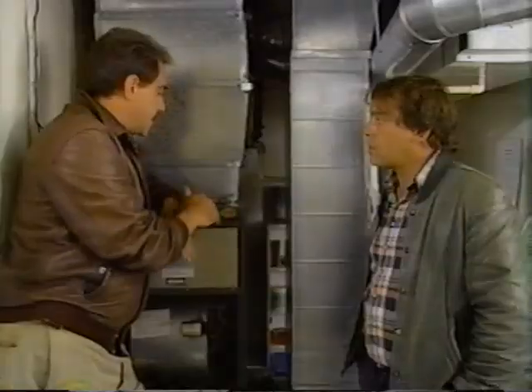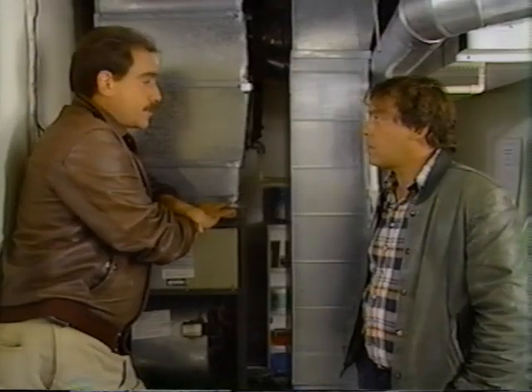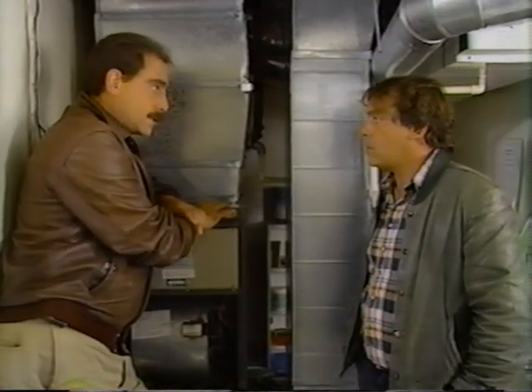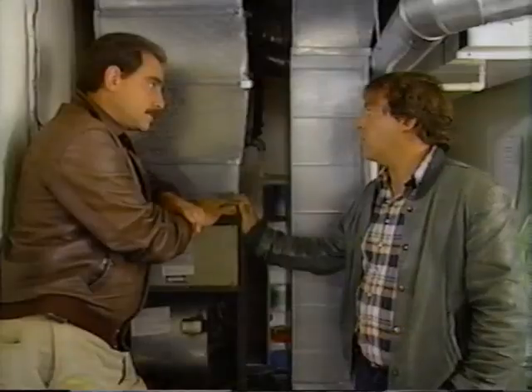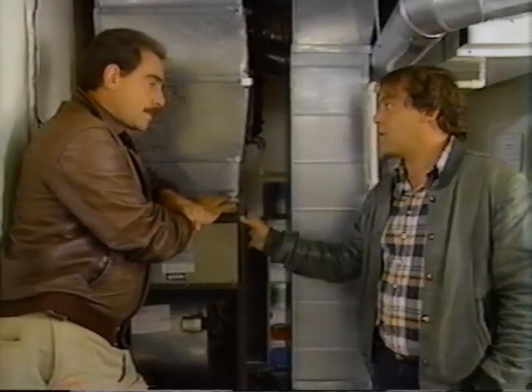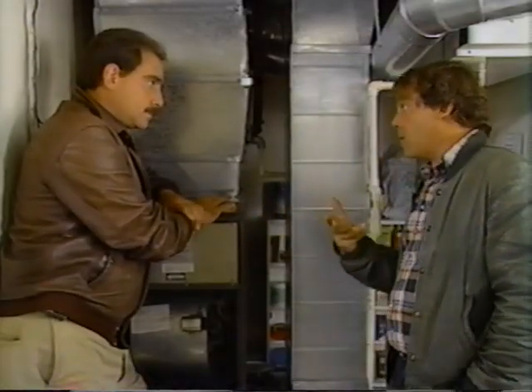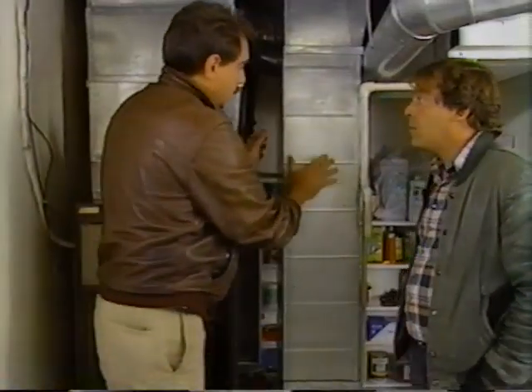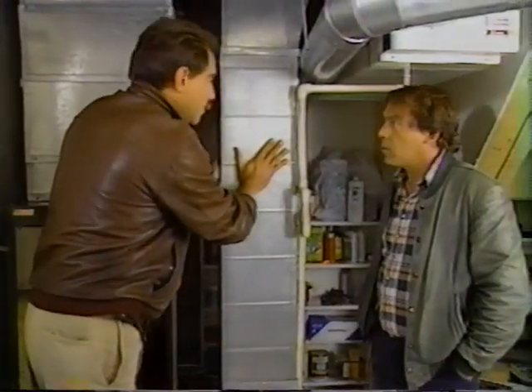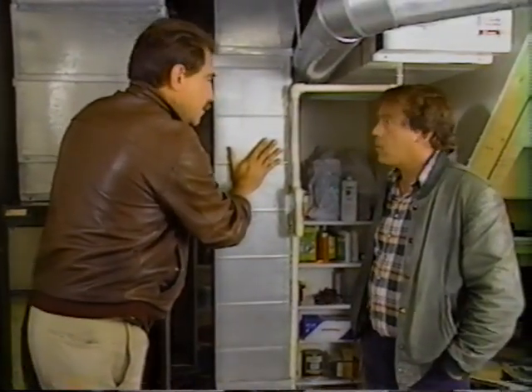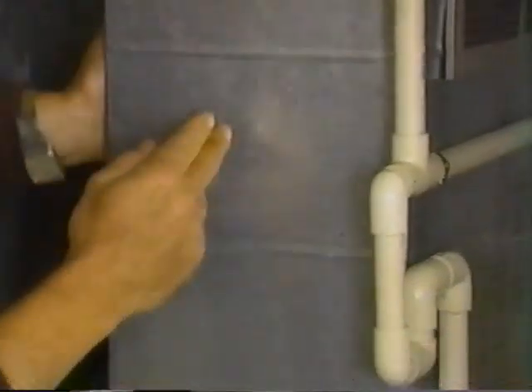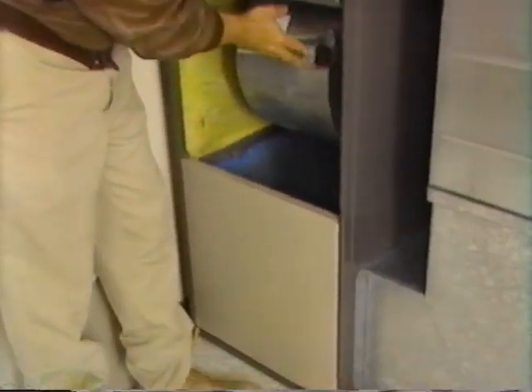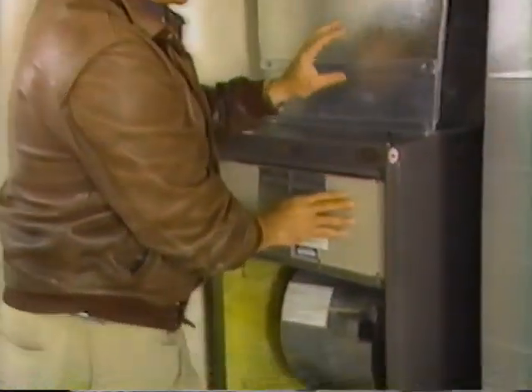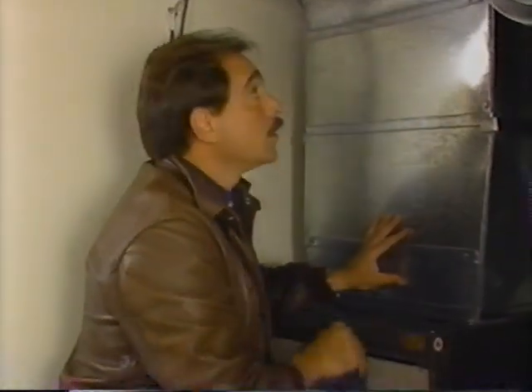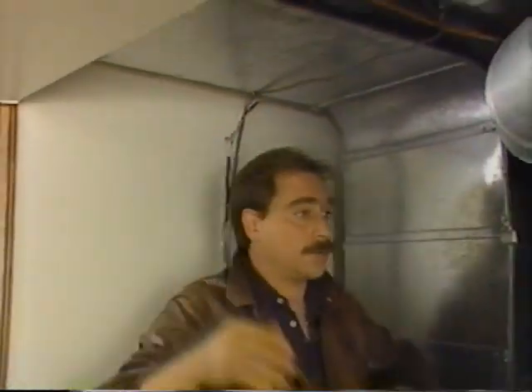And when you recognize that, a central electric furnace with the ductwork already connected to it can become quite a nice option. Ah, so the ductwork, the plain normal ductwork that you would need for this system can just be used to also take the fresh air around. How do you do that? Well, as we've seen, David, this is the return air plenum, and we are allowing fresh air coming into the building to enter the return air plenum, pass through that return air plenum into the bottom of the furnace, through filters, through the blower, through the coils, and then out through the supply air, which goes through the entire building and out to all the rooms.